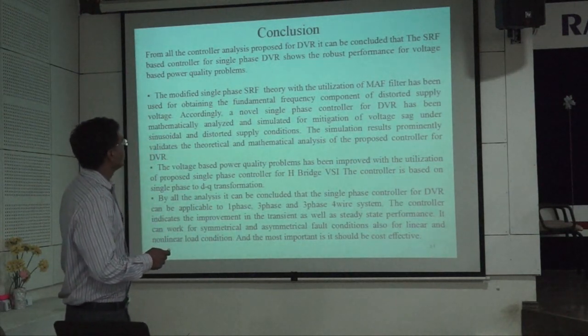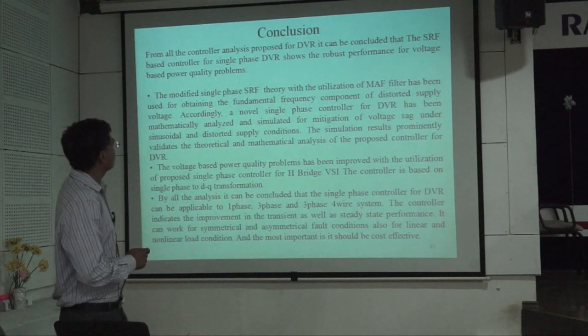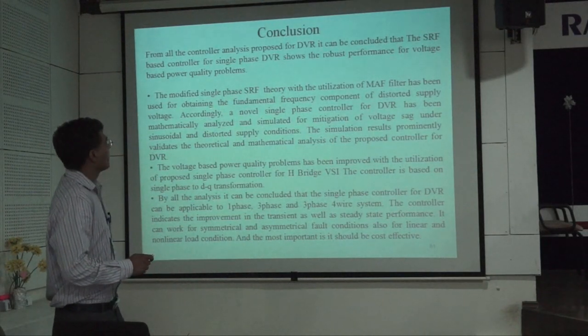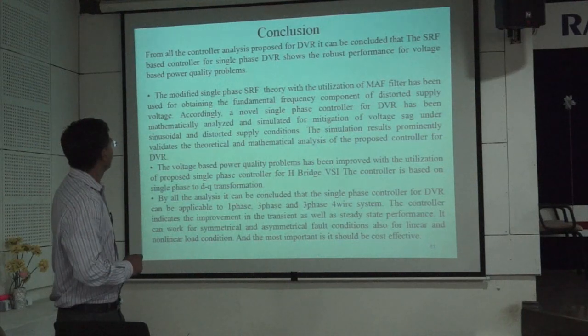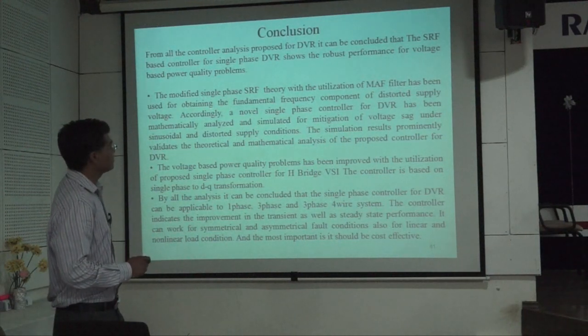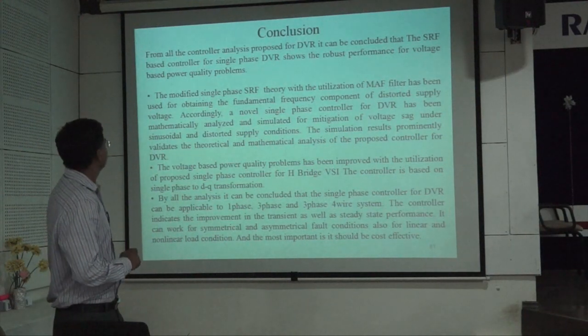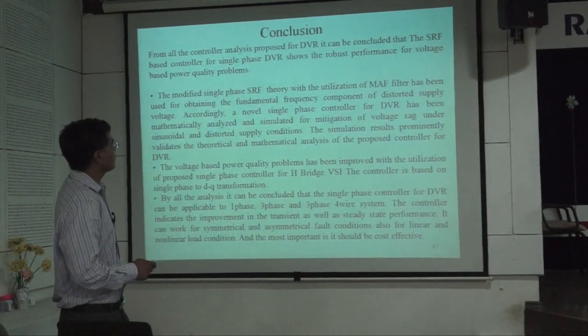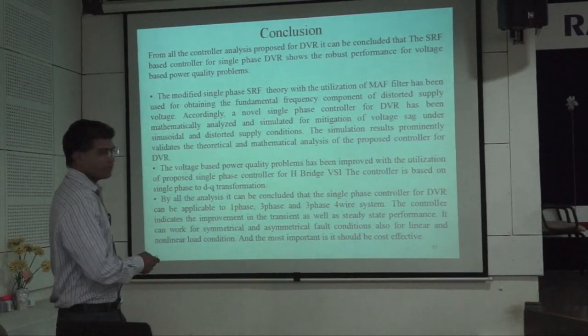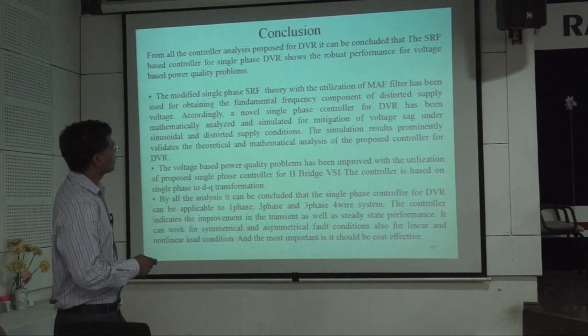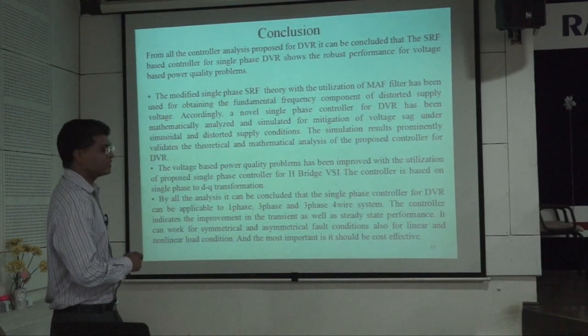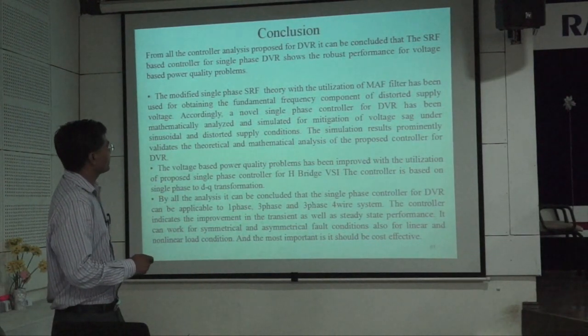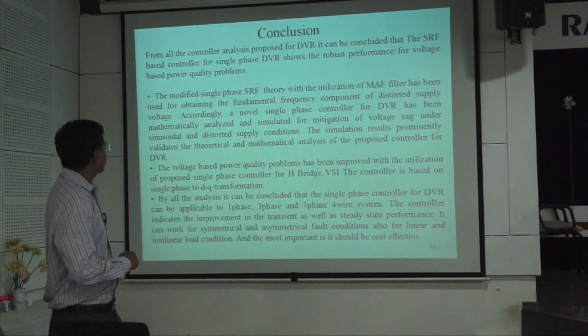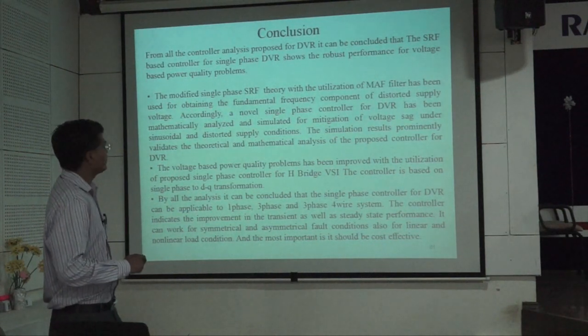It can be concluded that the SRF based controller for single phase DVR shows robust performance. For voltage based power quality problems, the modified single phase SRF theory with utilization of the MAF filter has been used for obtaining the fundamental frequency component of the distorted supply voltage. Accordingly, a novel single phase control for DVR has been mathematically analyzed and simulated for mitigation of voltage sag under sinusoidal and distorted supply conditions.